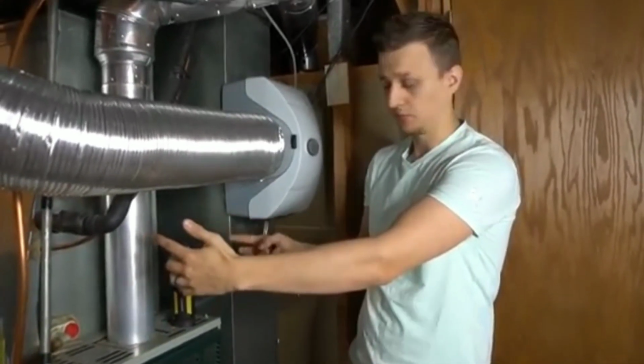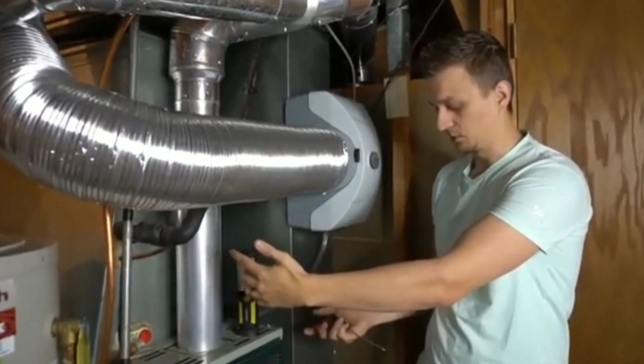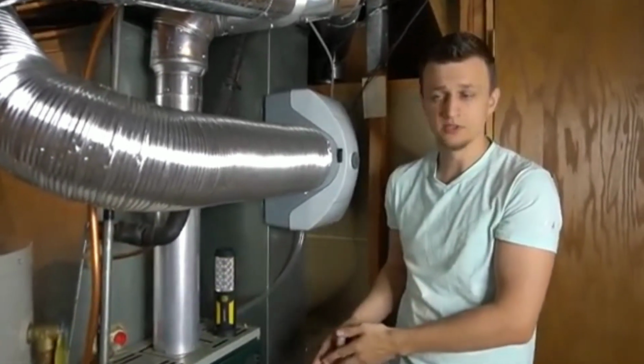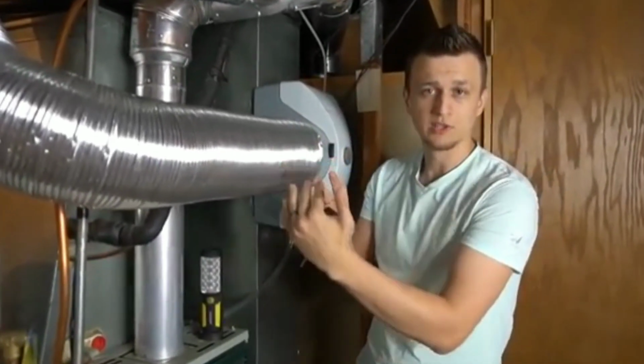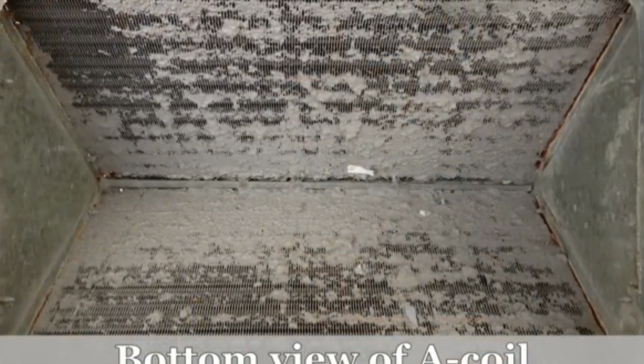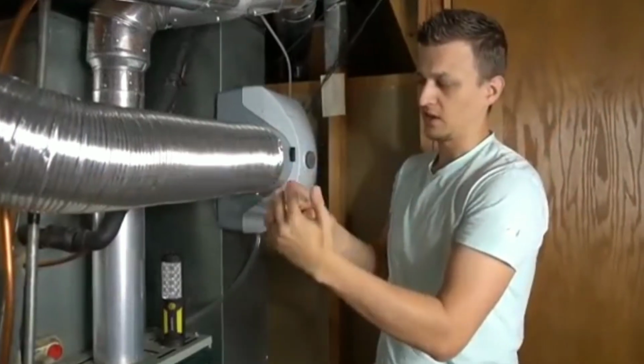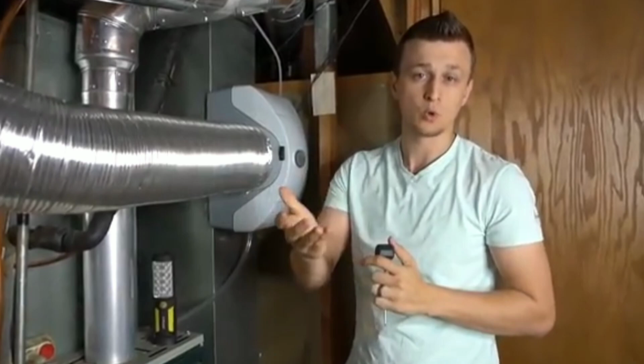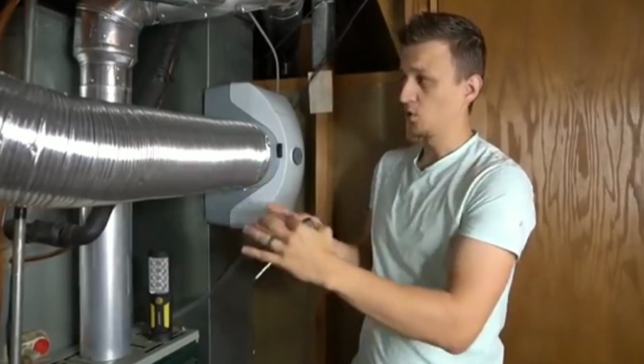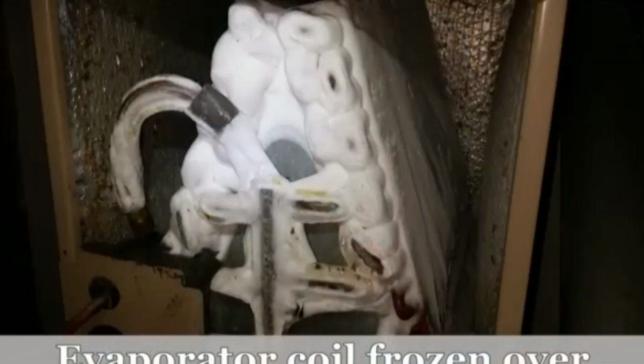Sometimes with time, if you're not very good at replacing filters, or if you have a fiberglass filter, that A coil will get plugged up with dust and whatever other debris gets by, and that restricts the airflow. And that restriction in airflow will also affect the operation of the air conditioner. It won't cool as well. Sometimes that coil can actually start to freeze over as well.